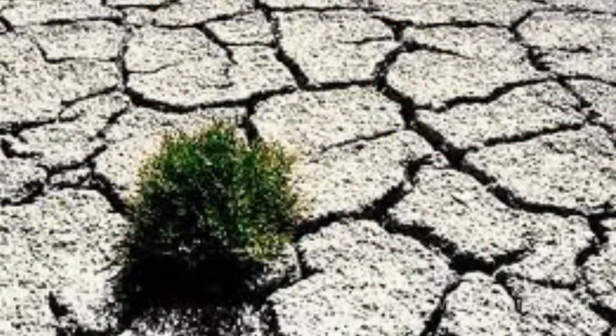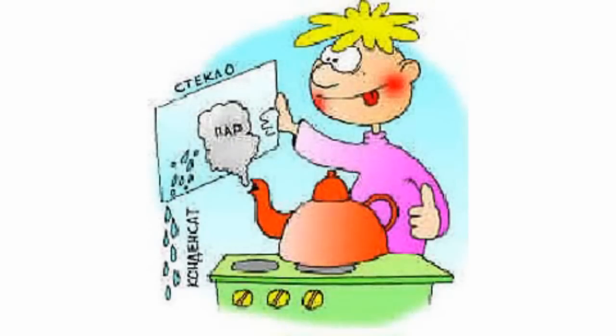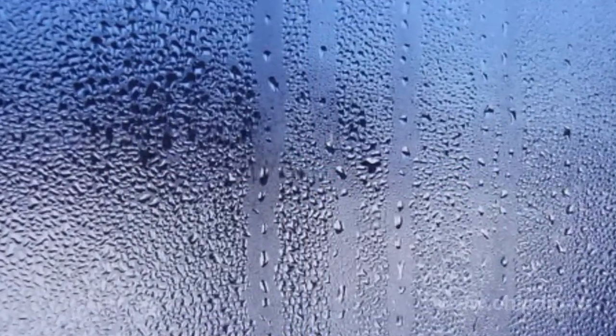Many of us have heard the term dew point many times, but few have a clear understanding of what it really means. One of the key characteristics of air used in various industrial fields is humidity. Air dryness and humidity depend on how close its water vapor is to saturation. If we cool down the humid air, the vapor contained in it could be brought to saturation and will start condensing. The point of vapor saturation is the first drops of condensed liquid, or simply the dew. The temperature to which the air must be cooled down for the water vapor contained in it to start condensing into dew is called the dew point.